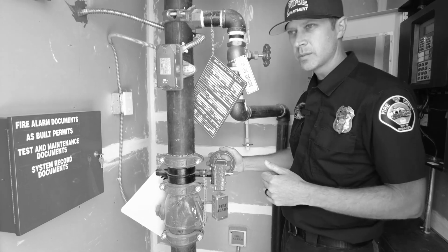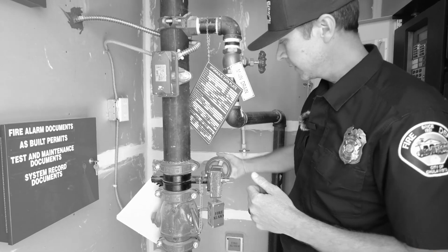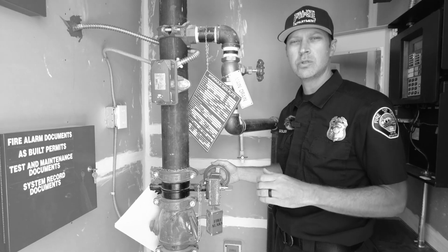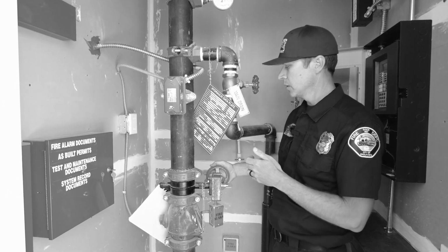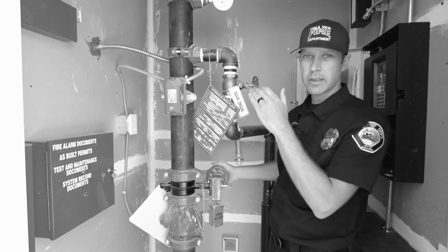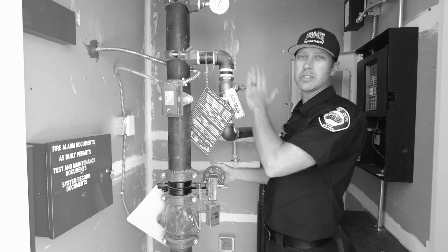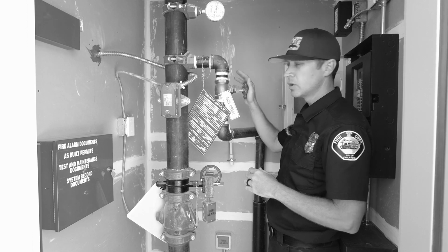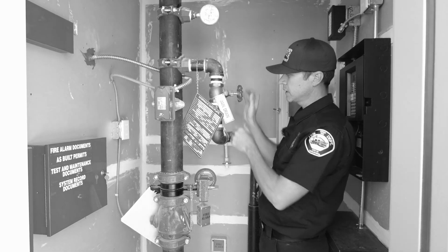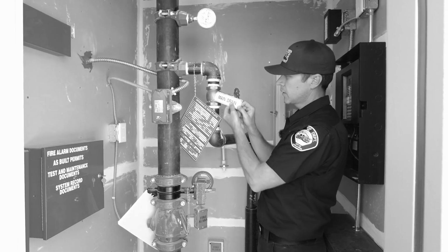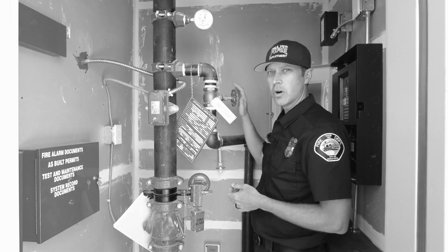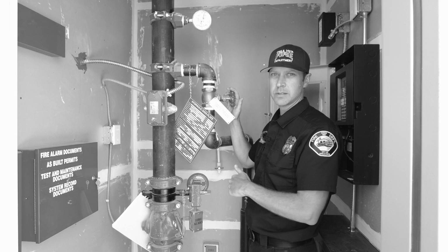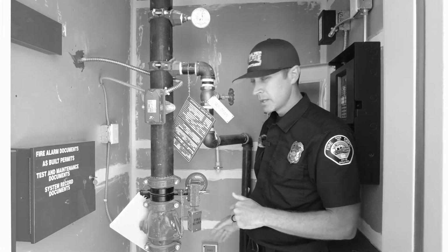Once you shut the system all the way off, the system will continue to drain through the fused sprinkler head or the broken pipe or the broken head. To get the water out of the system quicker, so it doesn't all have to drain through that head and cause more water damage, open the main drain. Main drains are on the riser and are usually identified by a nameplate. Open the main drain all the way and let the system drain until it stops.